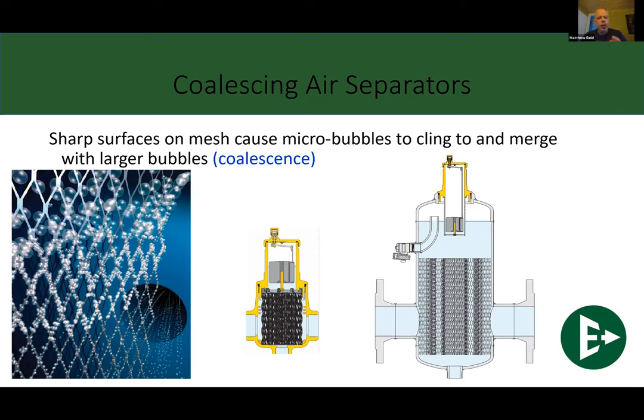With a high efficiency air separator, you will absolutely pull the air out of that cavity and eventually fill that air expansion tank with water under pressure. It's designed to do that. That's what these things are designed to do, is pull that air out. So like I said, manufacturers instructions do trump everything, but there are different ways.